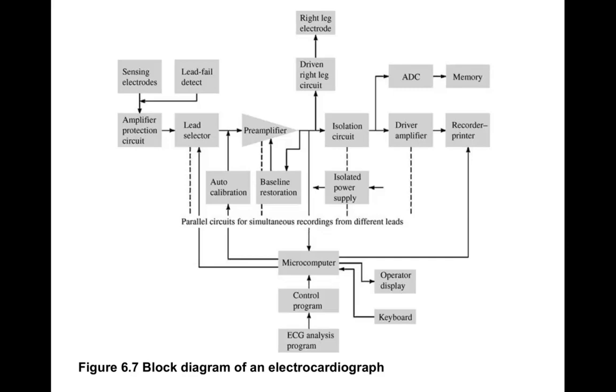So having a loose lead detector is important, and typically having some kind of display that says this is only a loose lead detector, so that people know not to freak out and just to tighten the lead, is also important. You then have your protection circuitry that basically prevents the circuitry that's going to make the measurement and condition the signal from coming back to the body.